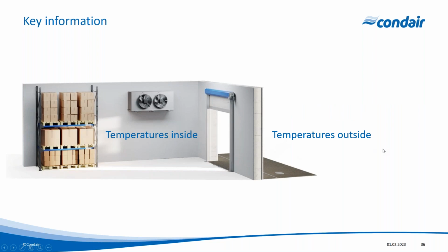And then we're going to need to know what is the temperature and humidity difference both inside and outside, ideally for winter and summer. And that is going to tell us the difference in vapor pressure between the two areas, and that in conjunction with the size of the orifice is going to dictate how much air is going to be forced into that freezer or cold store. And we know that air has a certain moisture content, and so we know that moisture is going to be deposited as ice on the cold surfaces, be it the ceiling of the cold store or the evaporator coil or the product.